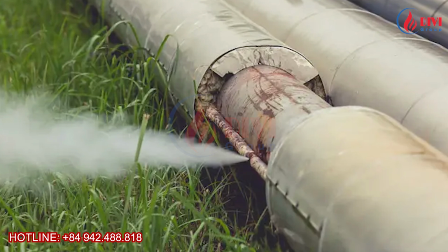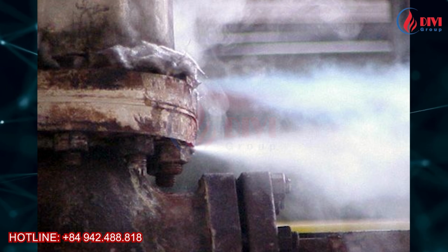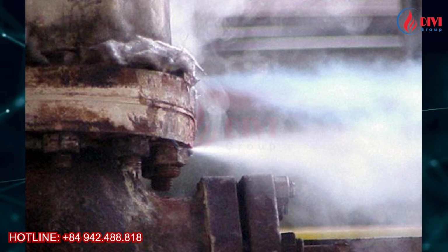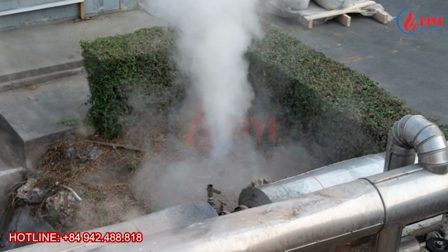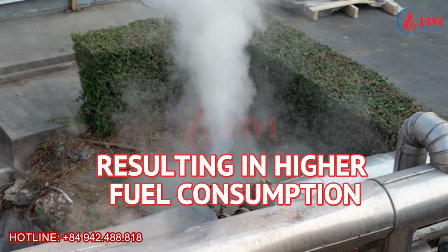Waste number 3, steam leakage in the system. Steam leakage is a very common issue in many factories. The problem is that many operators become so accustomed to it that they no longer notice it. If there are multiple leakage points in the system, the steam loss can become extremely significant. In addition, steam leakage reduces overall system pressure. The boiler must continuously increase its load, resulting in higher fuel consumption.